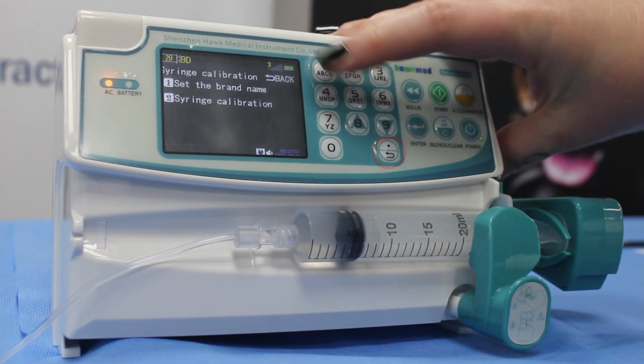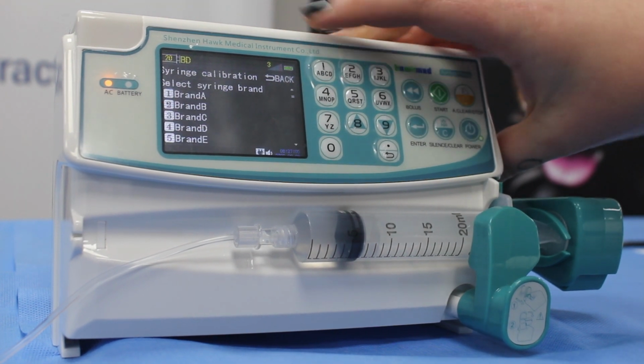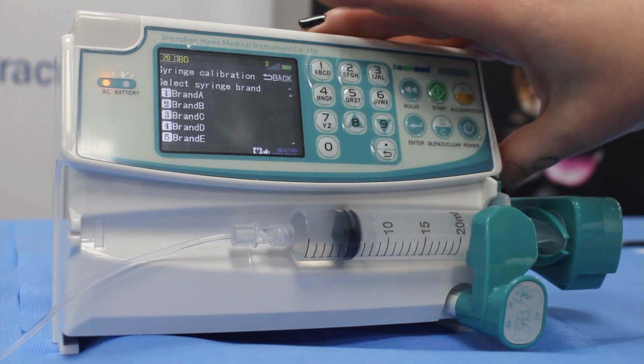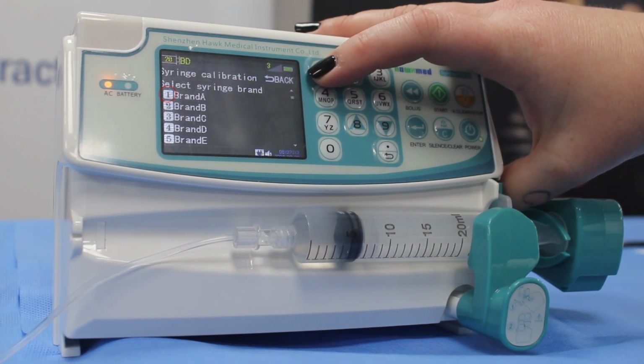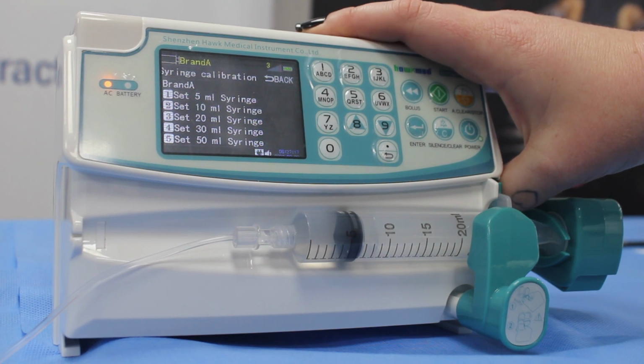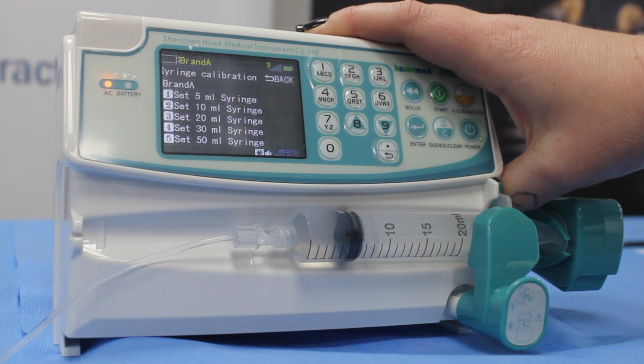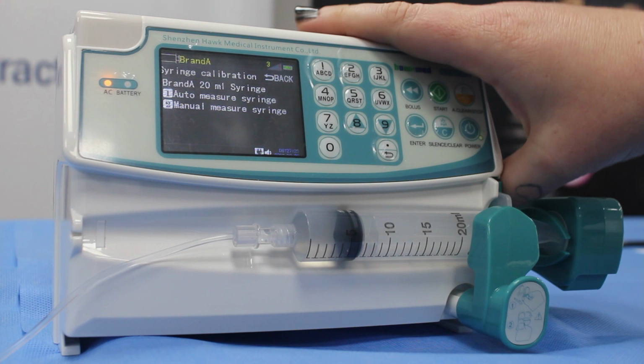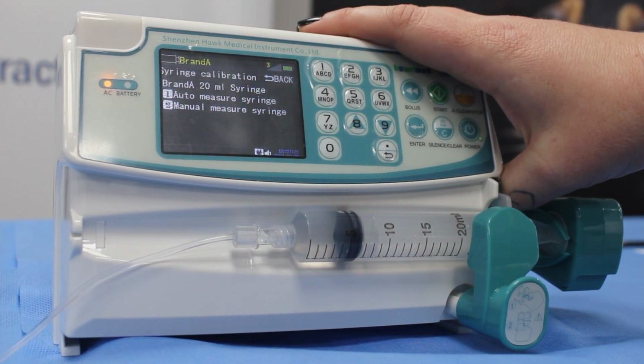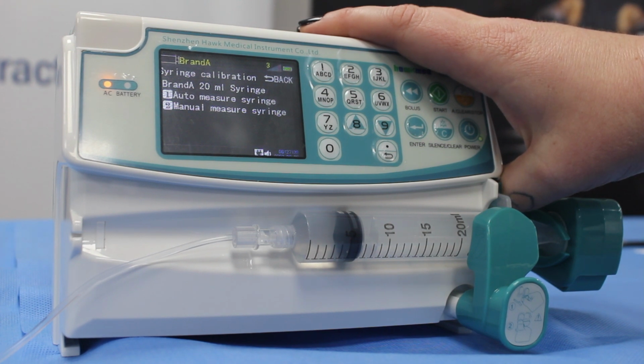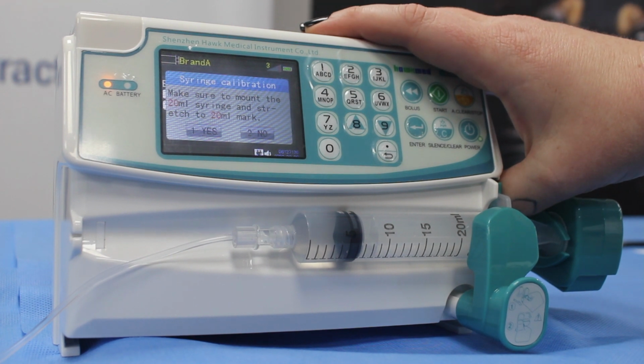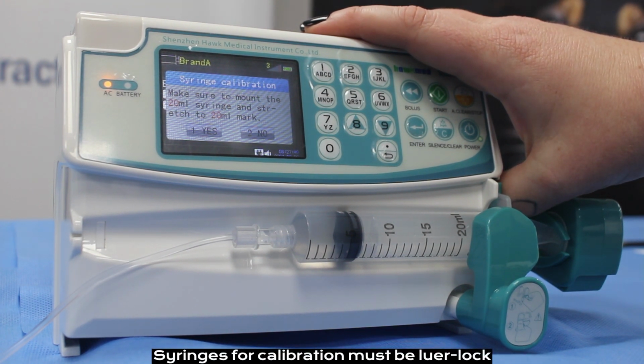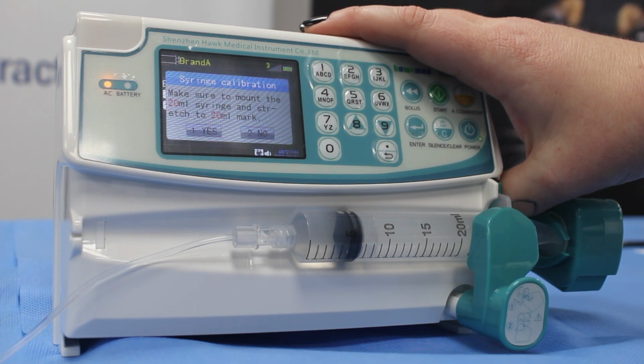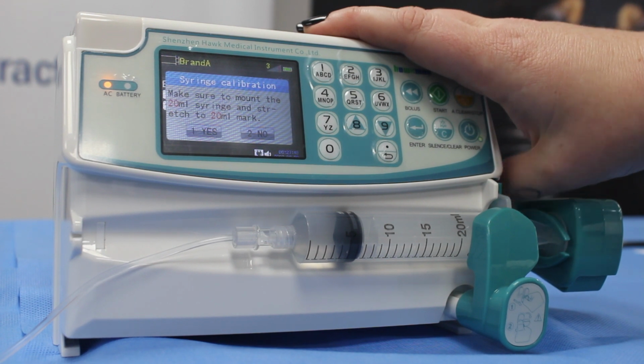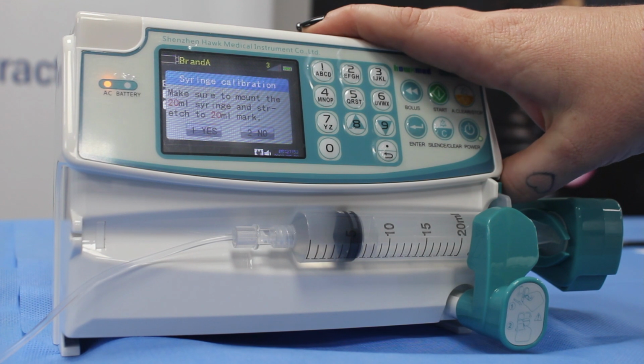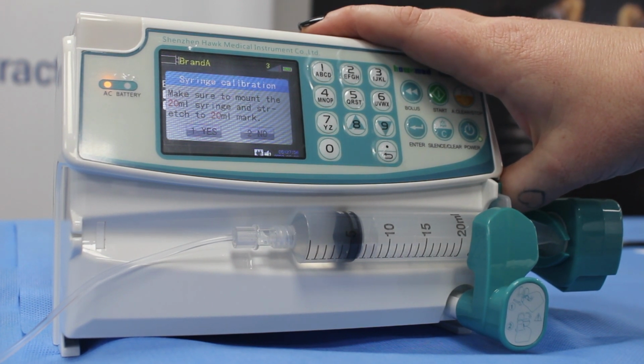This is how you can list the different brands if you're looking to add multiple customized syringes. Going back, we can see that there is syringe calibration under number 2. This is again where we have our customized list of the names. And if we were wanting to customize one, say brand A, we'd hit 1. And we can see this gives us the options to calibrate all the different syringe sizes. For example, if we went into number 3, which is 20, it's going to give us 2 options now for an auto measurement or a manual measurement of your syringe. To auto measure, we'd press 1, and you get a notice asking you to draw back your syringe to the 20 ml mark. I would do this just with air into the syringe, pop it into the syringe pump with the plunger control arm and the holding device in place, and then I'd press yes. The syringe would then calibrate to that size.